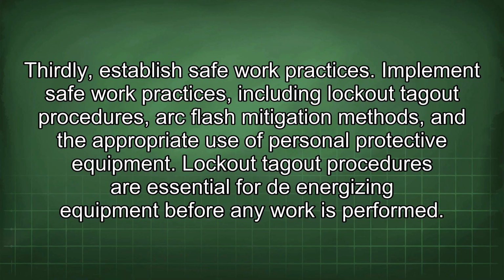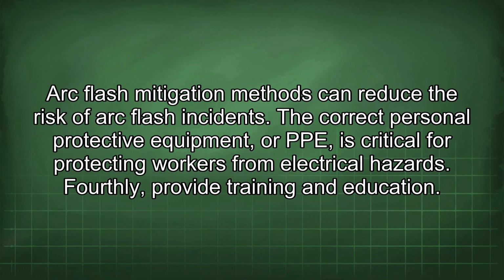Thirdly, establish safe work practices. Implement safe work practices, including lockout-tagout procedures, arc flash mitigation methods, and the appropriate use of personal protective equipment. Lockout-tagout procedures are essential for de-energizing equipment before any work is performed. Arc flash mitigation methods can reduce the risk of arc flash incidents. The correct personal protective equipment, or PPE, is critical for protecting workers from electrical hazards.